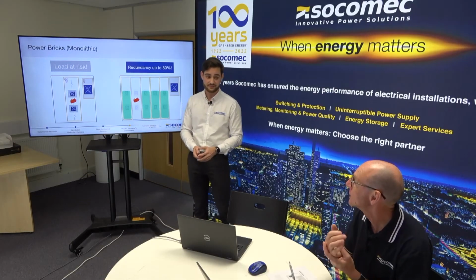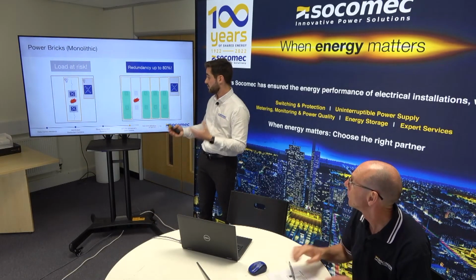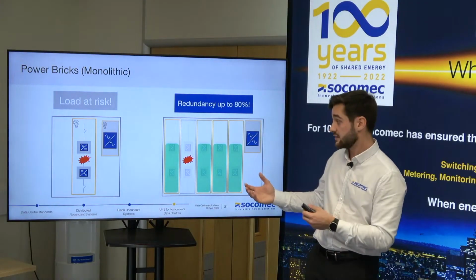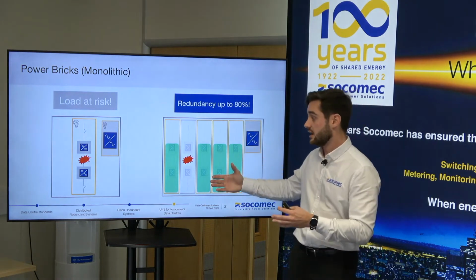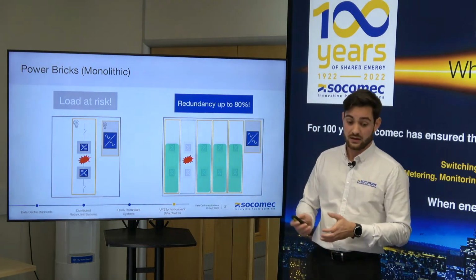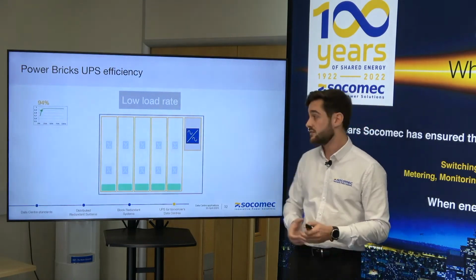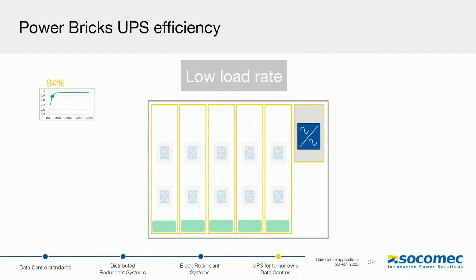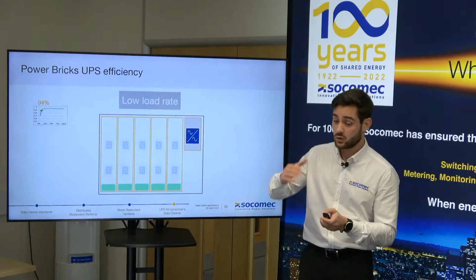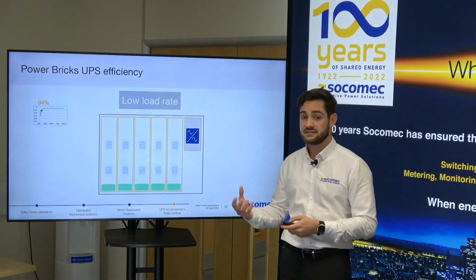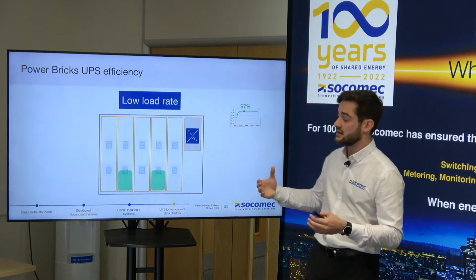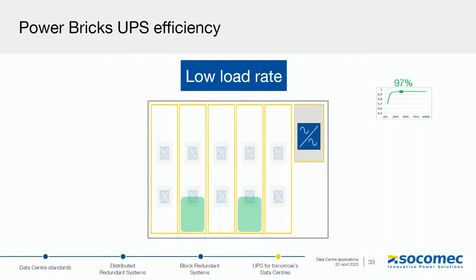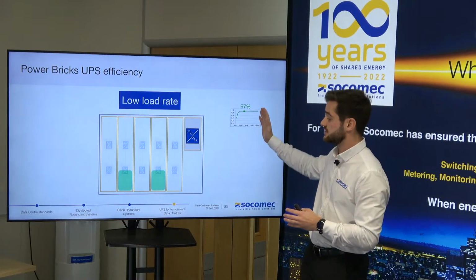Absolutely, so that's the solution. It's a significant improvement, and good for the footprint as well. Compared to a modular UPS system, the footprint of a monolithic would be reduced quite a lot. It's also quite good for efficiency. On a normal monolithic UPS system, when you've got a low load rate, it can impact the efficiency, which can be quite low. But with a bricks UPS system, as long as you've got enough bricks within the UPS system to cover the load, some power bricks can be put onto standby. The UPS will do that automatically to increase the efficiency of the system.